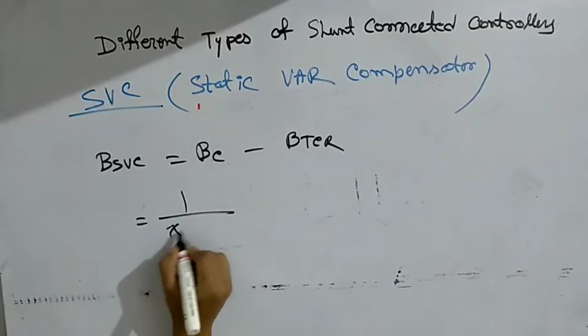The changing susceptance represents the total SVC susceptance necessary to maintain the nodal voltage magnitude at the specified value. Now SVC compensation may also be computed in terms of thyristor firing angle, however the additional calculation requires an iterative solution as the SVC susceptance and the thyristor firing angle are non-linearly related. So the steady state susceptance of SVC can be obtained as BSVC equals BC minus BTCR, which equals 1 by XC into XL, XL minus XC by pi, 2 into pi minus alpha plus sine 2 alpha, where XL equals omega L and XC equals 1 by omega C. Now since QSVC equals minus Vj square BSVC, we can write Qj equals minus Vj square, XC into XL, XL minus XC by pi, 2 into pi minus alpha plus sine 2 alpha.